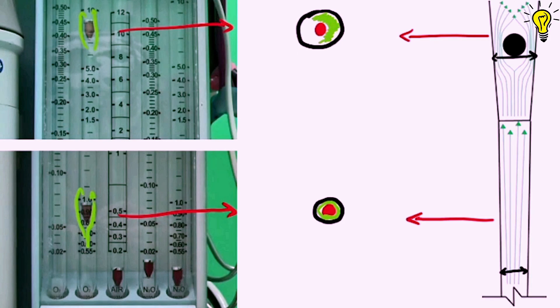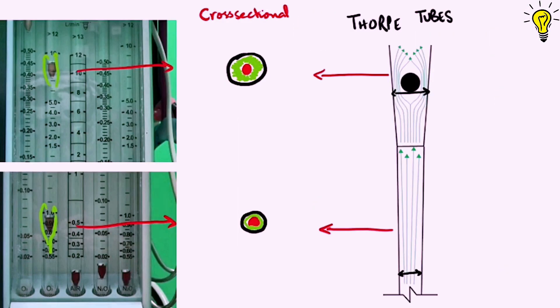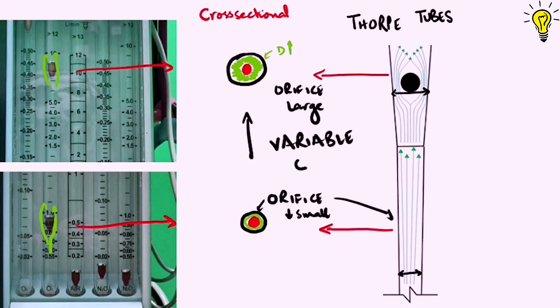And the orifice increases in the upper part, represented here in green area around the float. So since area of orifice in upper part is large, so less resistance and more flow can pass in upper parts. Since the orifice changes as we move up, it's called variable orifice. So now we know why they are called constant pressure variable orifice flow meters.